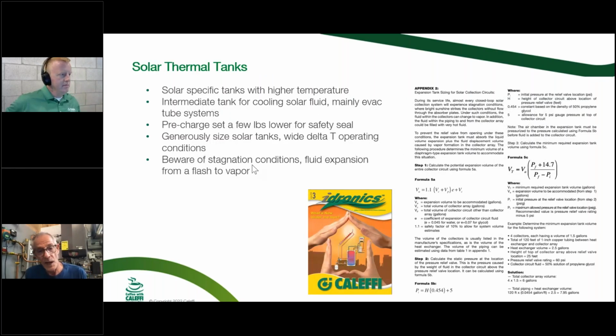And it gets even a little bit more complicated with solar, because the same thing will happen in a solar. Let's say you fill the solar system with 50-degree water. Turn the system on for the first time, and it's a sunny, warm summer day like today. I might get up to 170, 180 degrees out of that collector by the end of the day. In the wintertime, I could have that temperature of that collector be 0 degrees. So now I filled it with 55-degree water, and now I've got 0-degree temperature in that collector. Now I'm going to see a decrease in pressure on that gauge, and you're going to get a phone call: you've got to come out here, I've got a leak in my solar system somewhere, my gauge dropped down to 0.